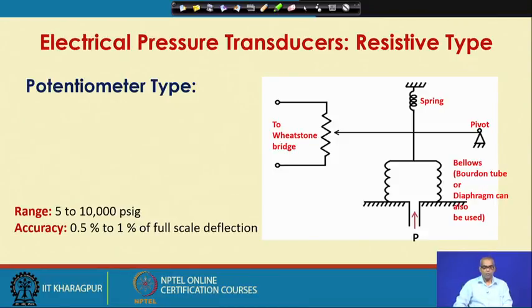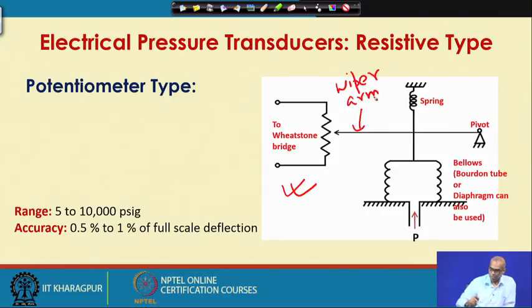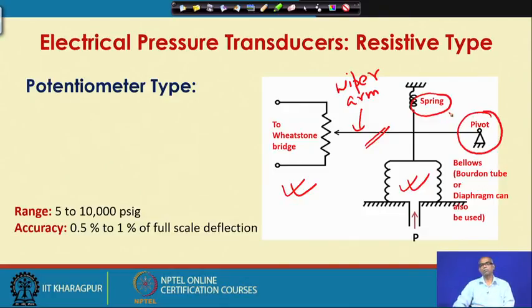So, the first resistive type electrical pressure transducer we will talk about is a simple potentiometer type. It consists of a precision potentiometer. This is the wiper arm, you have a bellows here. The bellows is connected to this wiper arm. We have also attached a spring here, and this wiper arm is pivoted. So, when I apply pressure inside the bellows, the sealed end of the bellows will show deflection.